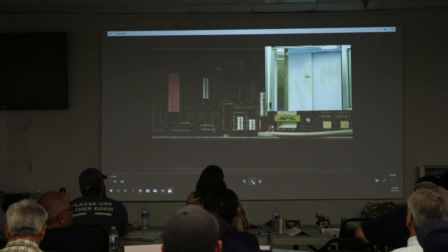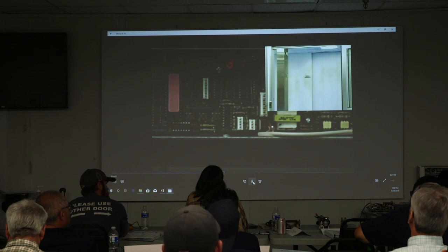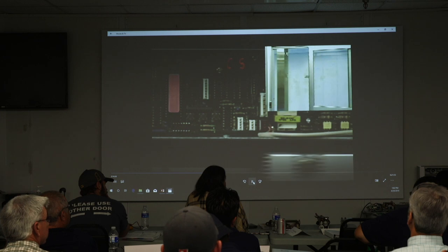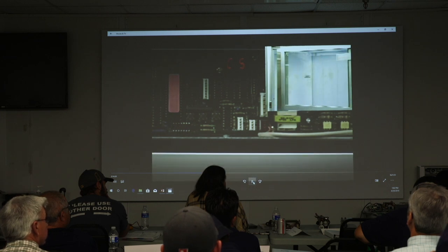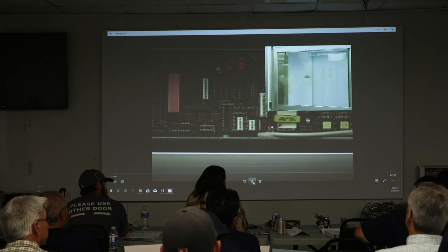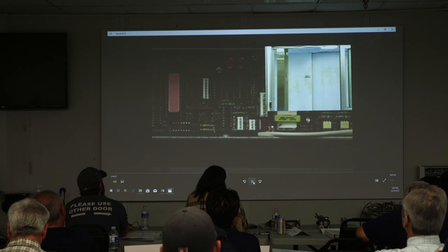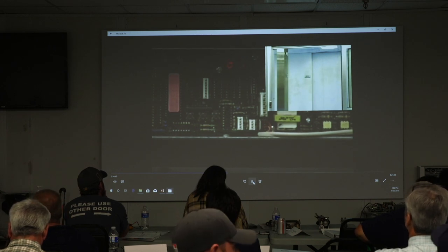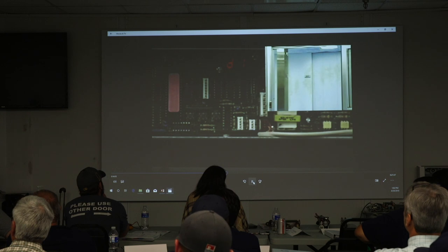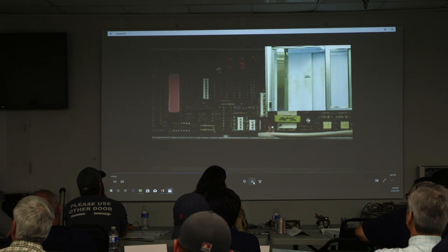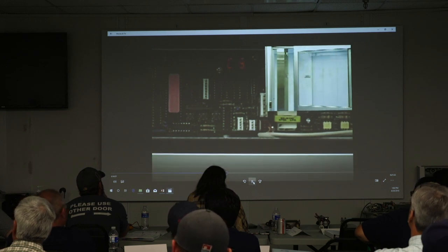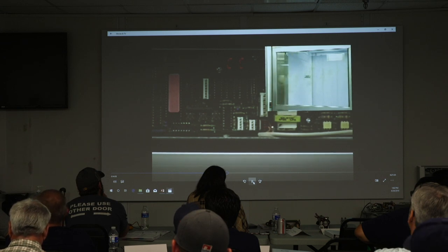So a lot of times on an install, you get the first door going, you want to go to the second door, you can put the first door on cycle test and just let it sit there and run for a few hours just to loosen up weather strip or something. So you have that cycle test ability to let the door run while you're doing something else. When it's in cycle test, it still responds to motion detectors, so you're not going to run over your public. If it sees somebody, it'll go back open. This door out here is in cycle test, so you're not going to...